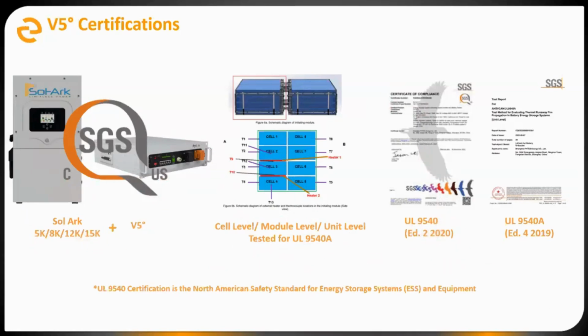Again, we have UL 9540. All of the V5 enclosures that I showed you a couple of slides ago fall under that UL 9540. It's basically up to 12 battery modules per inverter. So if you have one Sol-Ark 15K inverter, you can do up to 12 V5 batteries with any of those enclosures that I showed, and that whole system will qualify as a multi-part ESS under UL 9540. Let's say you add a second inverter to that example. Now we've got two inverters, and that means you can have up to 24 batteries and still maintain the certification.